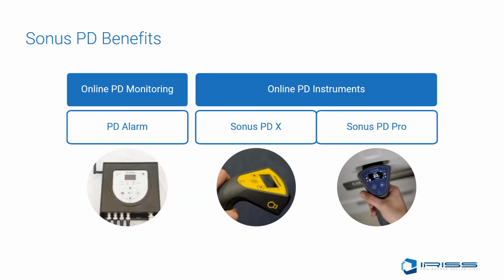IRISS is now proud to offer 3 different models of PD detection. First, with the Sonus PD Alert, a site can continuously monitor their hard-to-reach electrical assets with continuous monitoring, or use a handheld with routine routes on the assets. An improved noise rejection filter has been included in the new firmware, the Sonus PD Pro and the Sonus PDX, to allow the device to shift any non-electrical anomalies to a value of -6 decibels, letting the inspector know that the presence of the sound is not electrical or transient earth voltage in nature.